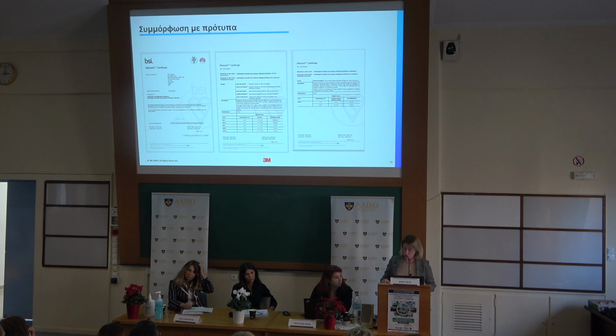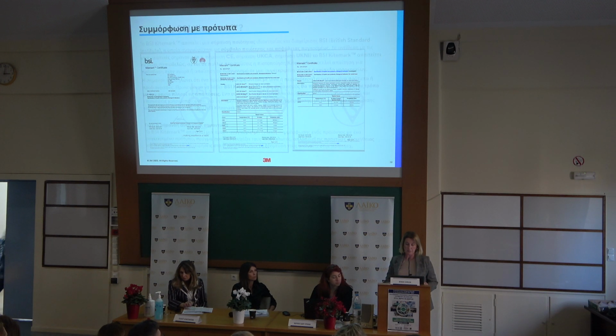And whenever there is a documentation, in this documentation the user should be able to see all the values which are approved by the standard. So it's important to know about the issuing body who is preparing this report, how they test and what they mention in the documentation. And again, these tests cannot be done in big sterilizers. So any document saying that these tests were done in big sterilizers will not make any sense, because a hospital sterilizer is not a good tool to provide these results.